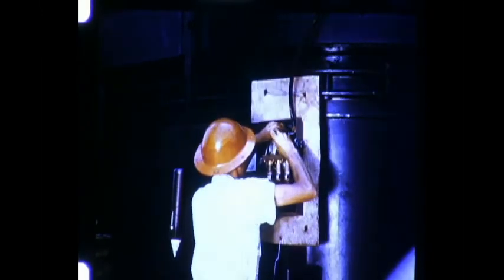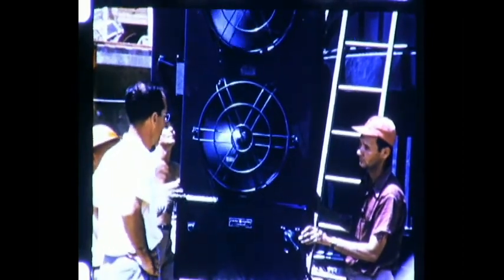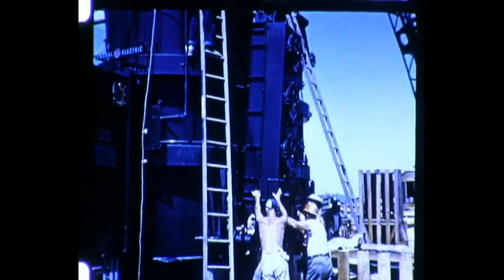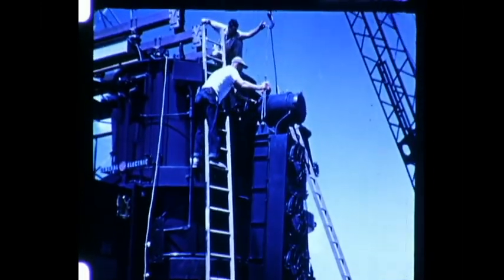In order to check the direction of fan and pump rotation of each cooler, a temporary 440-volt line is brought in and connected to the power supply terminals in the control housing at the bottom of the unit cooler. With the cooler raised so that the pump impeller is visible from the rear, the control power switch is turned on and off quickly while pump and fan rotation are checked. Now then, after the connecting elbow is bolted to the bottom of the cooler, the connection to the upper valve is made directly from the pump housing, and the cooler is now bolted both to top and bottom tank flanges.